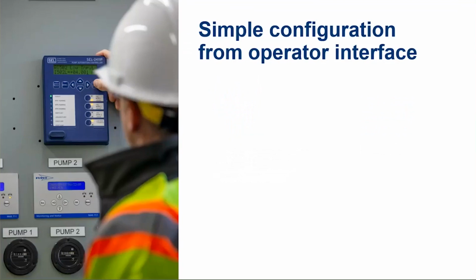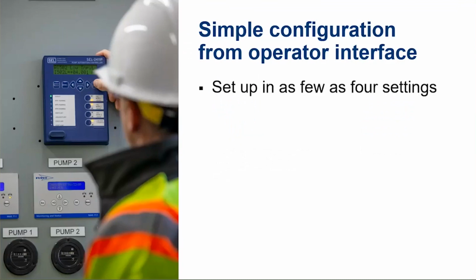So simple setup is something that we have been focusing on from the beginning of this, when this product was first released back in 2016. And with the latest firmware, we've added some more simplicity. So we have a feature called Station Settings that you can set up the lift station application in as few as 4 settings. It's kind of an interview process. You answer a few questions: duplex or triplex, how are you doing level control for this application, what kind of phase monitoring are you doing on this application? And then you're done. And it creates that custom application settings file just for you so that the station can come up and run.